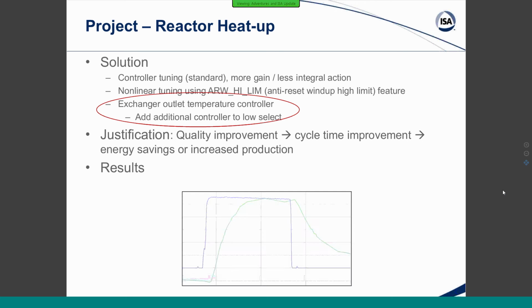So results, here's what that controller looks like. The blue is a change in set point, and the green is our exit temperature. They track really, really well, with much less dead time and lag time than we had on the controller with just the reactor temperature.